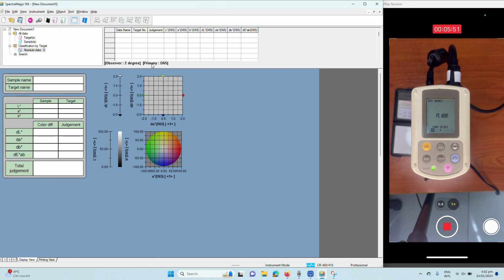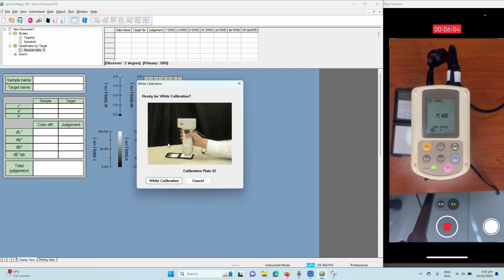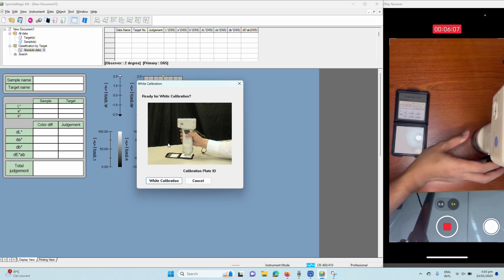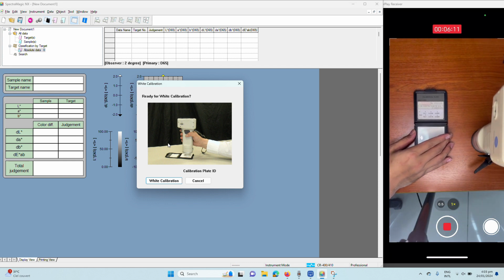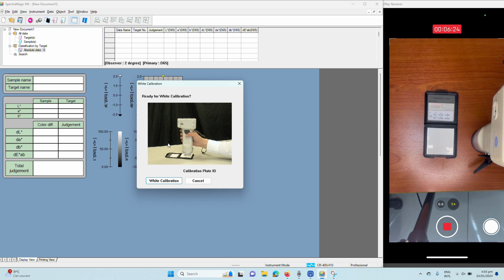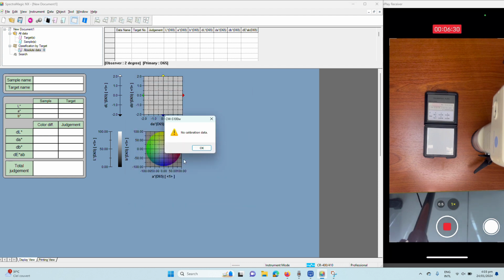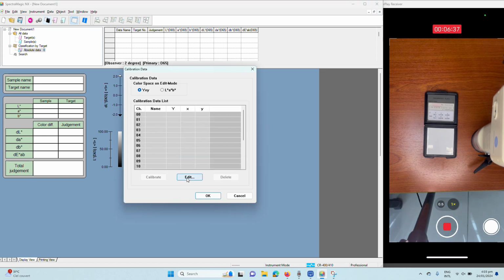Okay, so now you already set it, and now you can start to do calibration. In order to do calibration, just go here and click calibration. It will tell you to use the white plate here, which each device comes with. Usually for the CR400 you can have multiple white plates, but the best thing to do is to use the same plate which came with the device itself. This way your device is calibrated correctly. Now, using white calibration, of course we don't have data as we reset the instrument. So now we can just input the data. There we go.